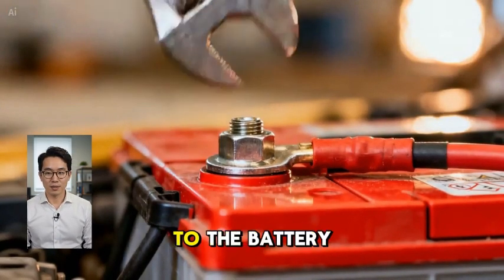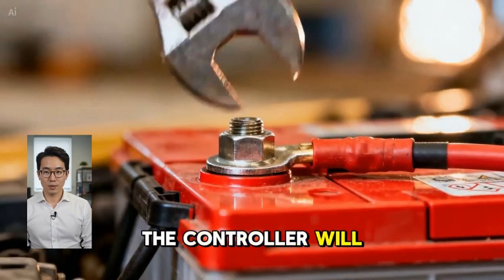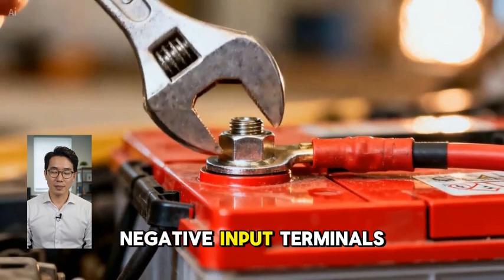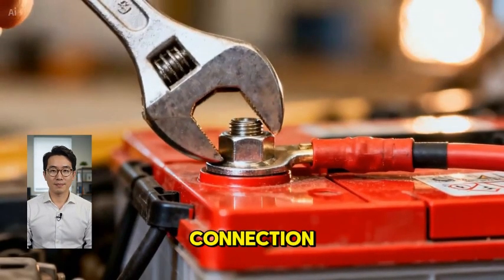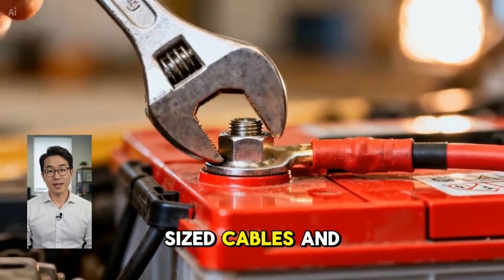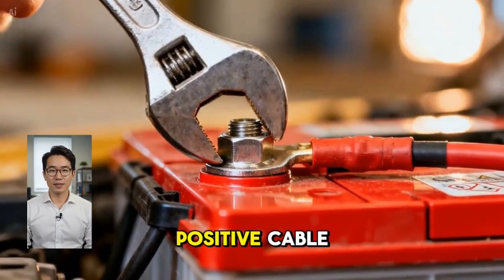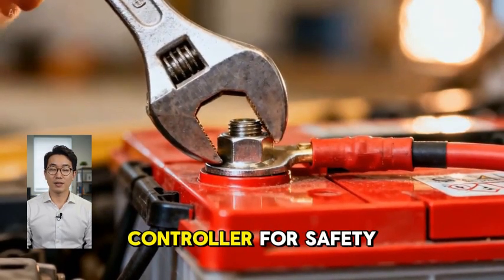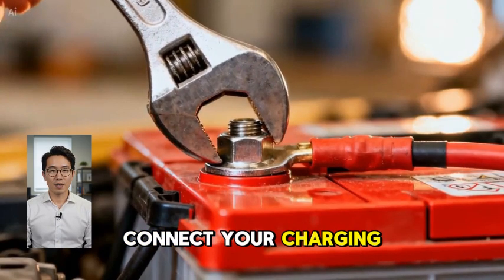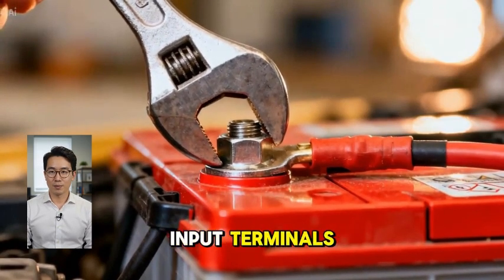Connect the charge controller to the battery bank. The controller will have clearly marked positive and negative input terminals for the battery connection. Use appropriately sized cables and install an inline fuse on the positive cable between the battery and the charge controller for safety.